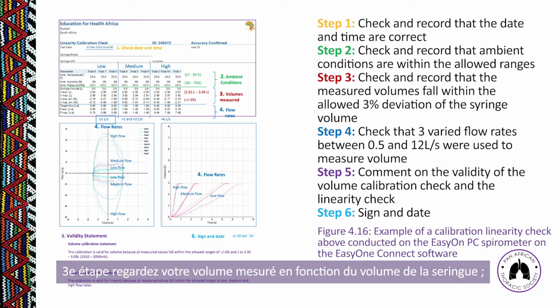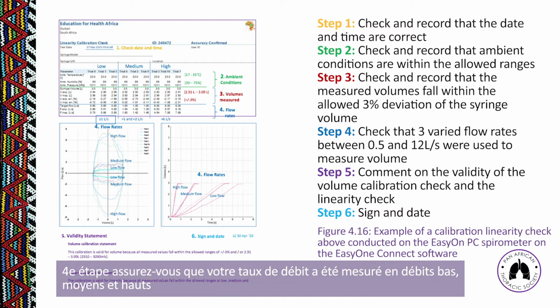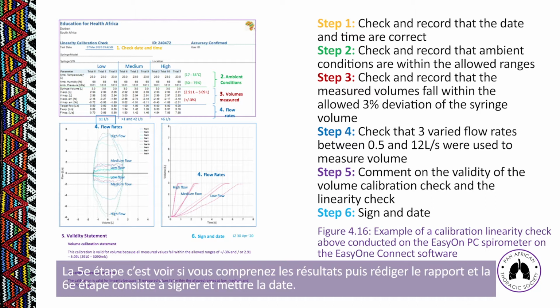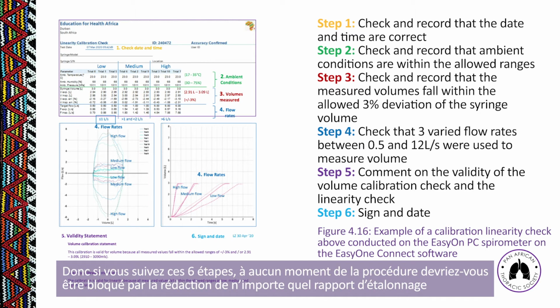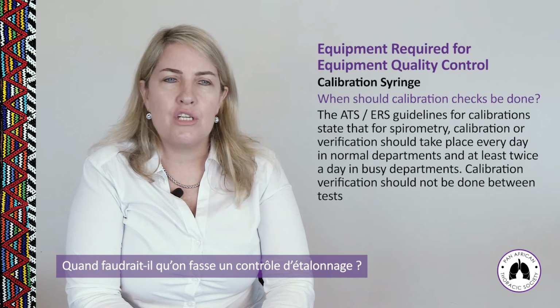Step number 3, look at your measured volumes versus your syringe volume. Step number 4, look at your flow rates to make sure that you used a low, medium, and high flow. Step number 5 is understanding whether or not this is valid and writing a statement on that. And step number 6 is signing and dating. So if you follow those 6 steps, you should never be lost in terms of reporting on any calibration report at any stage. When should you do calibration checks?